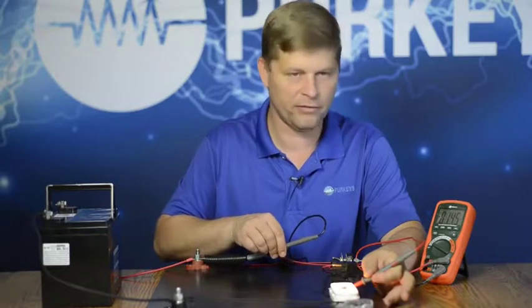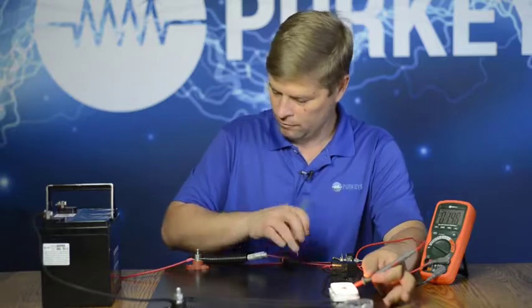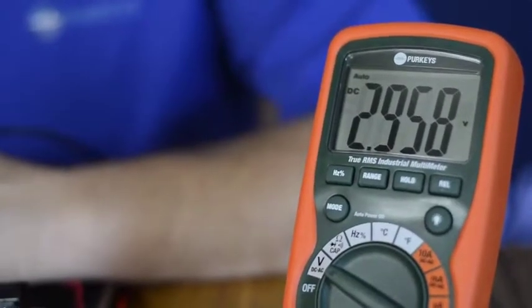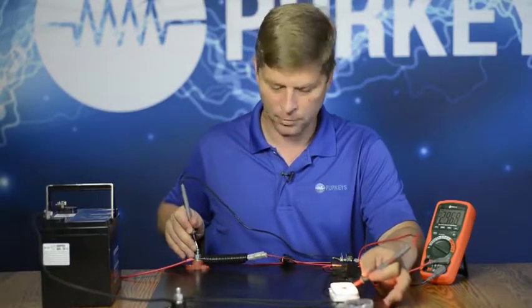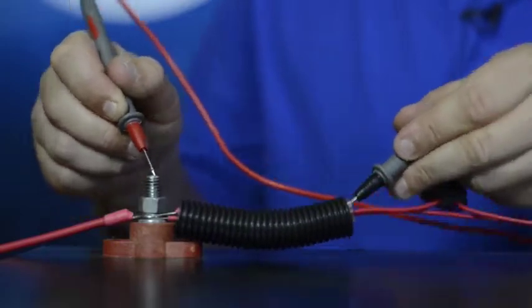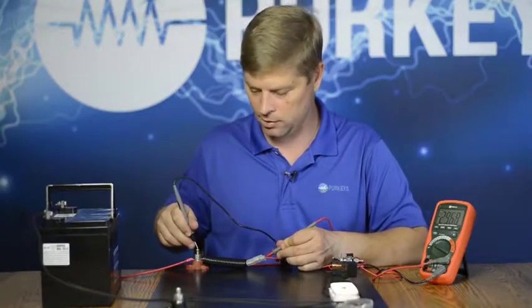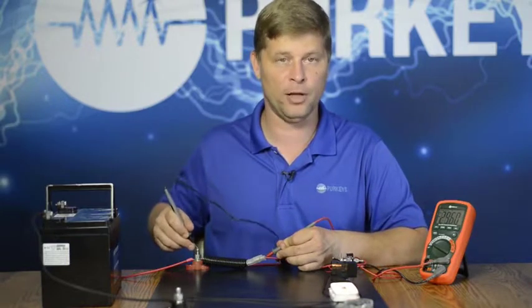I picked up a little bit, still very little voltage drop. I go all the way over here to my other junction stud. Suddenly there's where my voltage drop is. You see we've got almost three volts between here and here. That tells me somewhere in this part of the circuit I've got either a bad connection or I've got high resistance. Something is impeding that flow, so that's where my problem is.